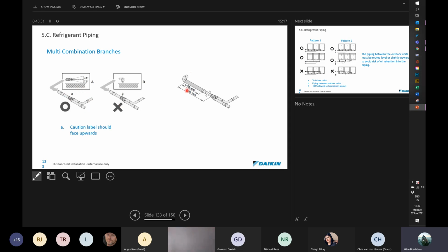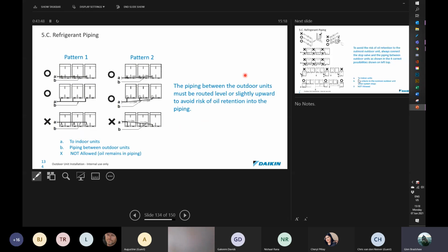They must be horizontal. You do need the 500 mils minimum straight piping into it, but once you come off this bend, you do not need 500 millimeters and then a bend. You can go straight off into that. That is the one time you break the 500 millimeter rule, and that is when installing at the condenser. And I'll show you if we go to the next slide. If you look at the diagrams supplied in the manual, they show the T-piece, or this is now the ref net, directly in line with the service valves. Okay, you do not need to mount them back 500 mils. Right, so just take note of that. These T-pieces, they do represent the outdoor connections, which are now ref nets.